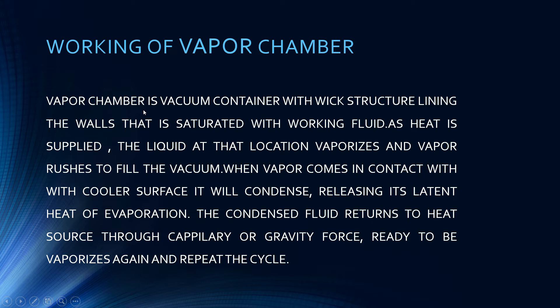Now we will see the working of the vapor chamber. A vapor chamber is a vacuum container with a wick structure lining the walls that is saturated with working fluid. As heat is supplied, the liquid at that location vaporizes and vapor rushes to fill the vacuum. When vapor comes in contact with the cooler surface it condenses, releasing its latent heat of evaporation.